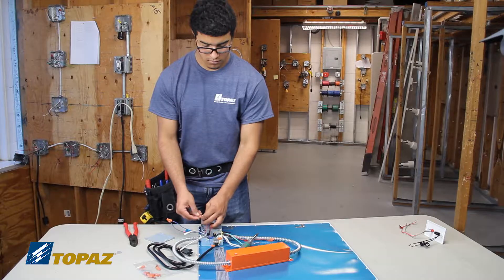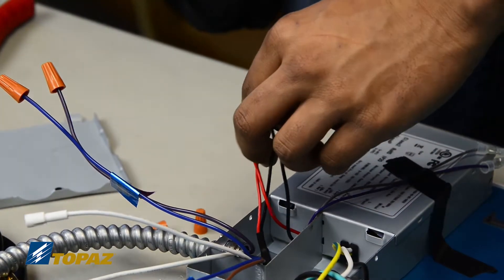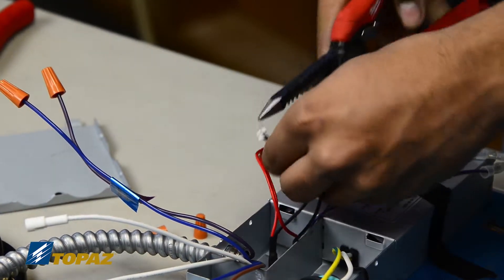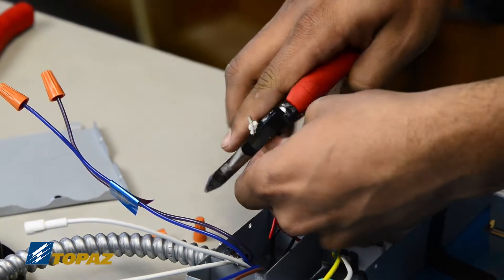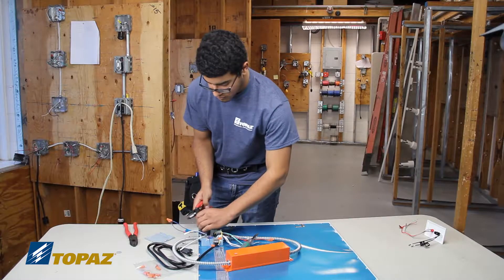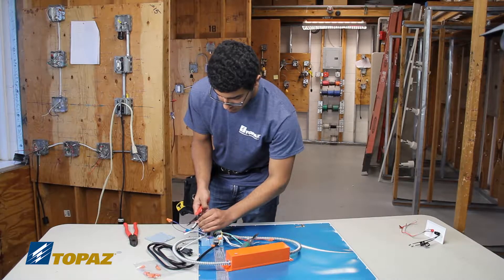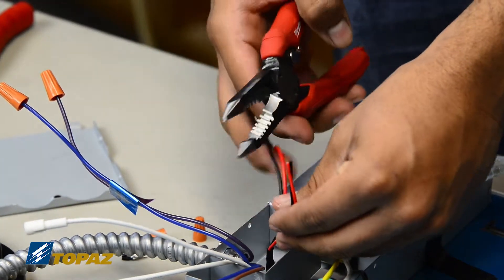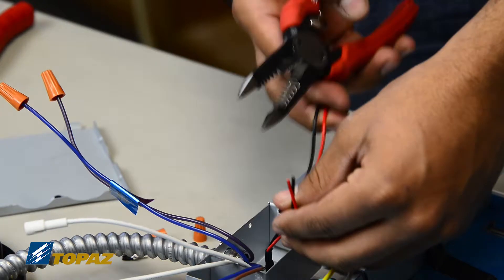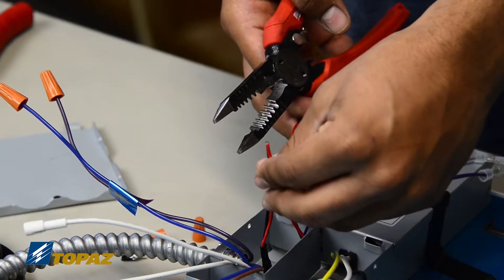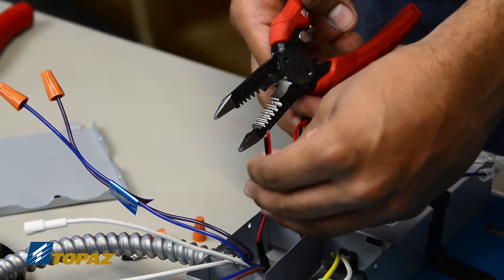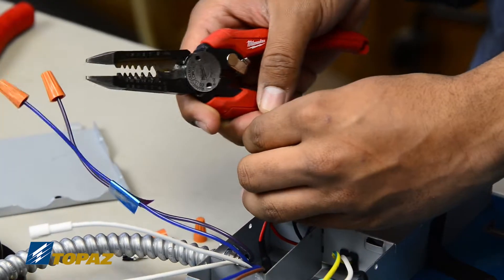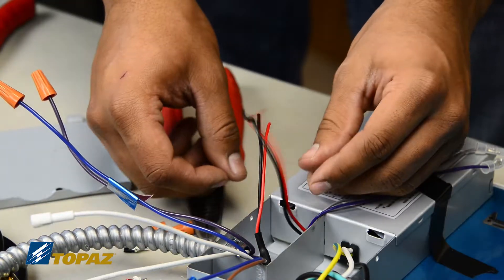Starting with the class 2 compartment, we're going to go ahead and separate the leads by removing the wire nuts. We're going to cut the ends off and restrip the wires. Now that we've separated them we can easily see the two leads that go to the driver, black and red, and the two leads that go directly to the LED array.